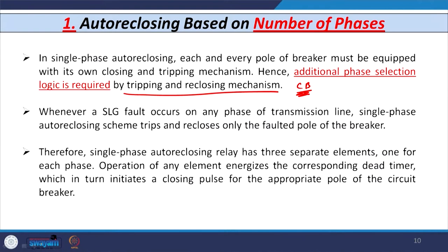For example, if a fault occurs in the R phase, only the R pole of the breaker opens while the other two healthy phases — Y and B — remain closed. The single phase auto reclosing relay has three separate elements, one for each phase. Operation of any element energizes the corresponding timer which gives the closing pulse for the appropriate pole of the circuit breaker. Single phase auto reclosers are slightly costlier than three phase auto reclosers.